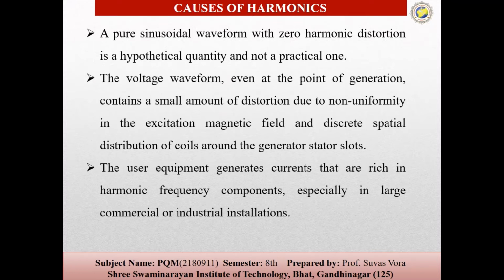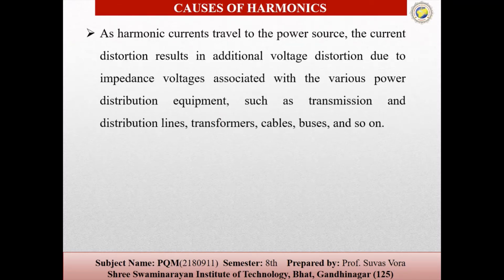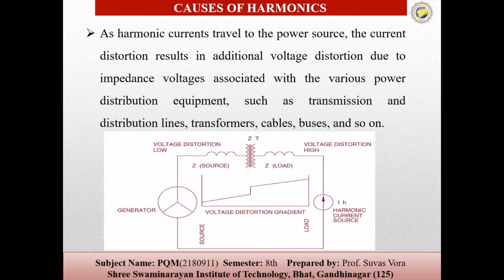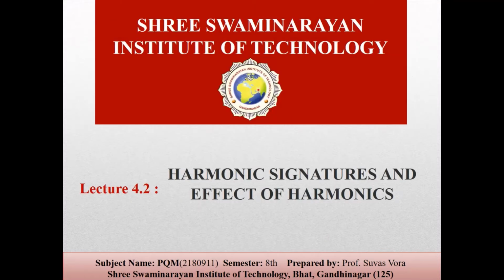Now, causes of the harmonics. So the harmonic current travels to the power source and the current distortions result in additional voltage distortions due to impedance. So the lines, transformers, cables, buses and so on are the affected parts of the system. So now today's topic is the harmonic signatures and the effect of harmonics.